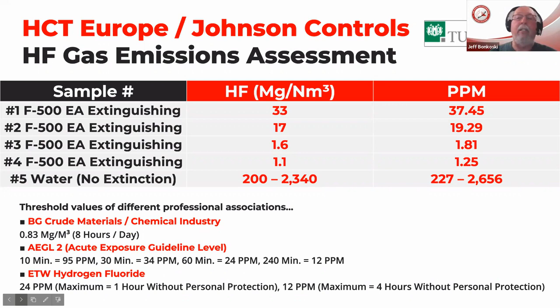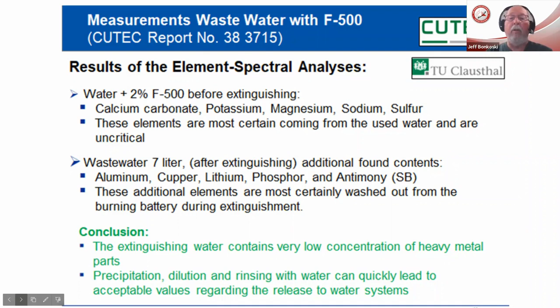When we look at the wastewater runoff, much less water is needed to extinguish these batteries. The water plus 2% F500 concentration shows what was found in the water before extinguishing. After extinguishing, with only about 7 liters of wastewater, they found some additional metals, but the conclusion was that the extinguishing water contained very low concentrations of heavy metal parts. By adding and diluting and rinsing the water, they can reach acceptable values so it can just be released into normal wastewater treatment facilities.